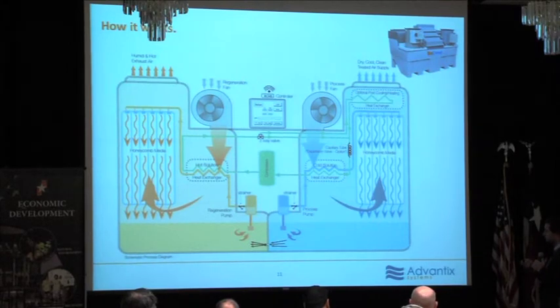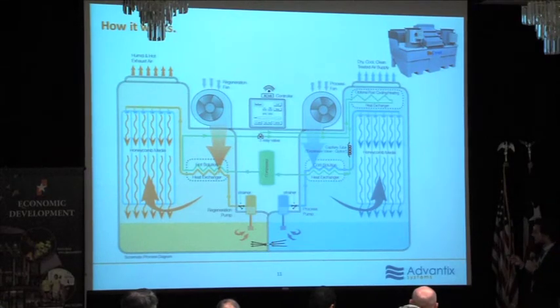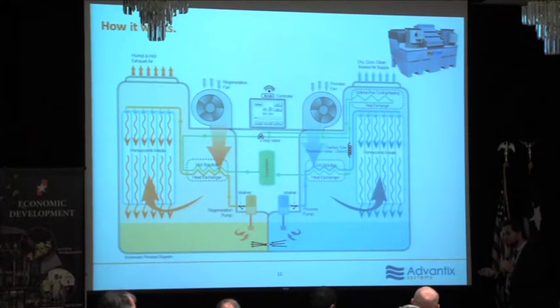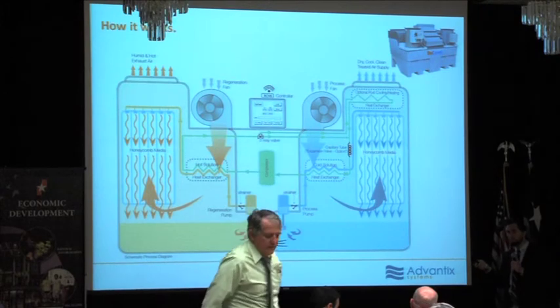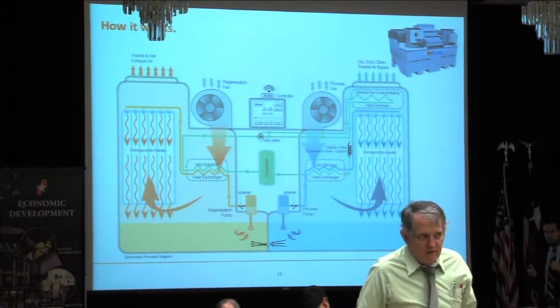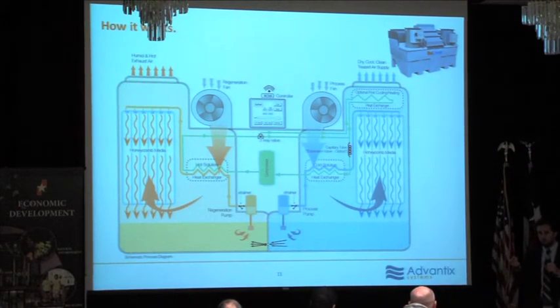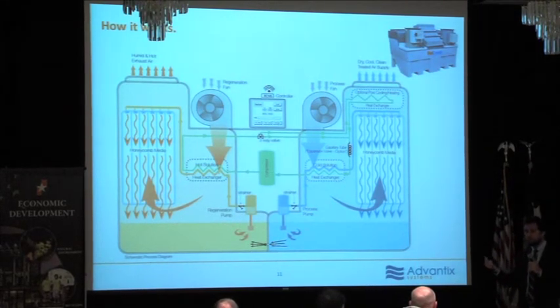And then what were the other things you asked about the materials? The piping and the honeycomb media. Piping is polymer tubing. Honeycomb media is corrugated cellulose. Unique thing about that corrugated cellulose, and I tell people that and they think, okay, it's tower fill, I need to replace it every 2 years. What degrades a wood fiber is two things, either ultraviolet light or microorganisms, specifically mold. Mold is what eats wood fiber.